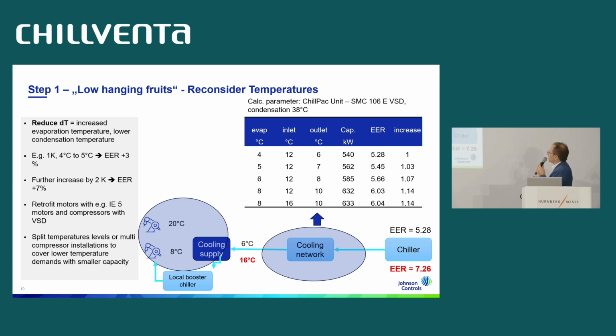And I've calculated this here. If you go even higher, you're going up to 7%. And even if you can manage to go even higher to 10 degrees Celsius, for example, outlet temperature by evaporation, you have a 14% increase directly with the same equipment. So this is calculated with a ChillPac from our company, a unit with an SMC compressor. This is the same unit, the same equipment, but running at higher temperatures. And you save money.